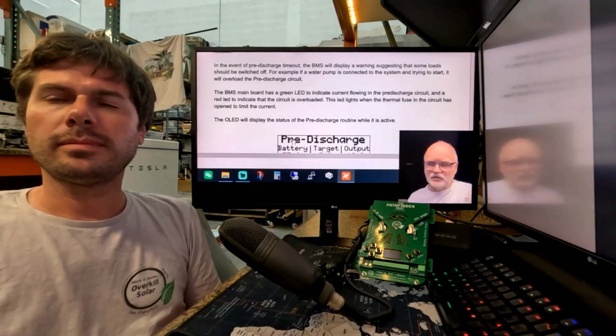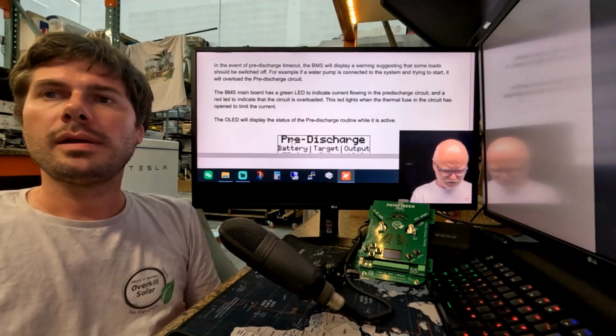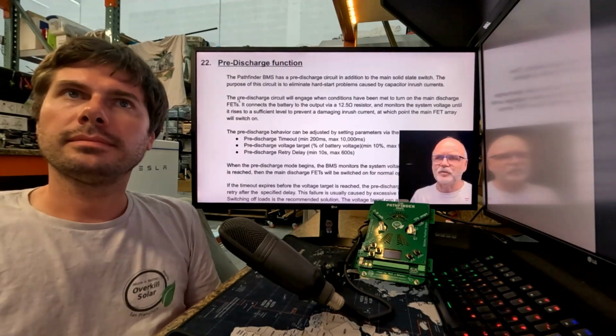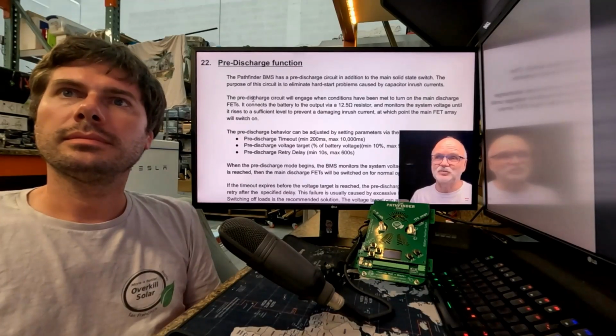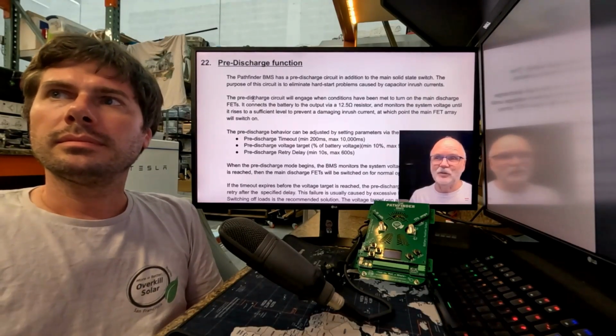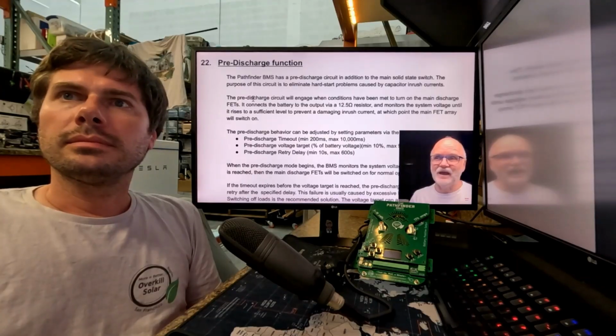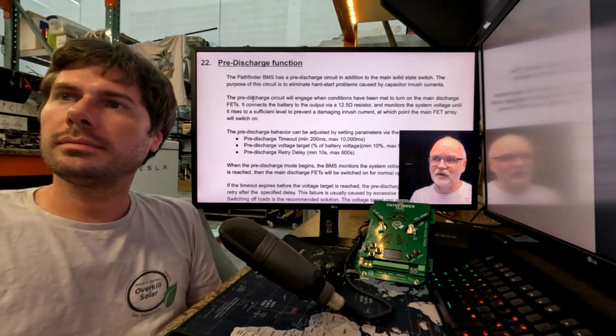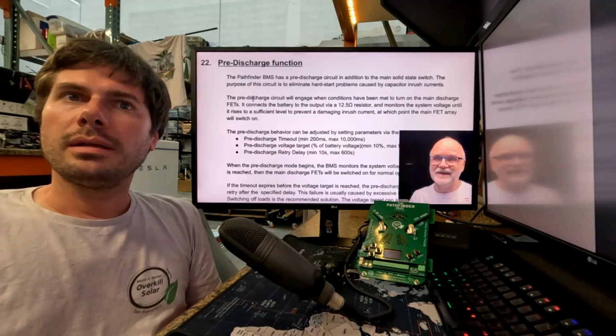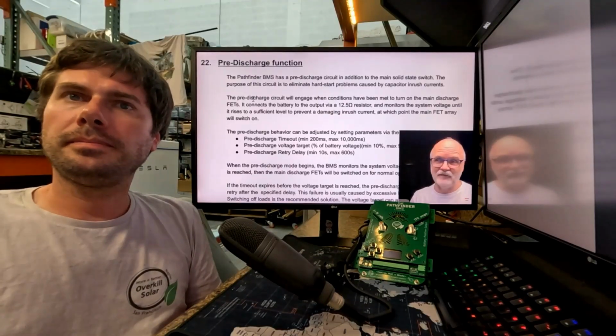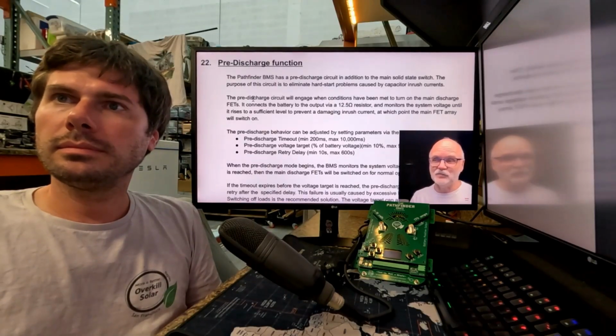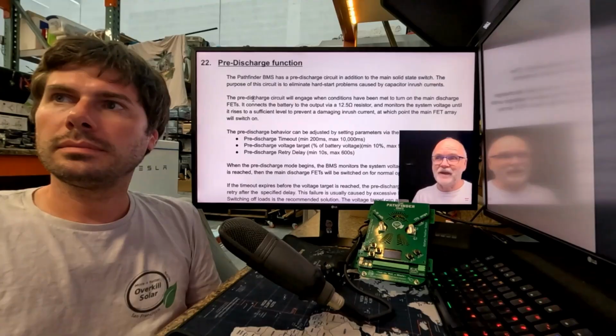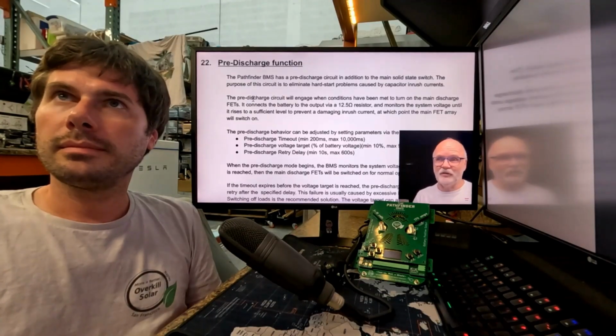The BMS also comes with a pre-discharge function. The pre-discharge circuit engages when conditions have been met - it connects the battery to the output via a 12.5 ohm resistor and monitors the system voltage until it rises to a sufficient level to prevent a damaging inrush current, at which point the main FET array switches on. I think most BMSs have this these days - they can determine if it's a short or an inrush current into an inverter.